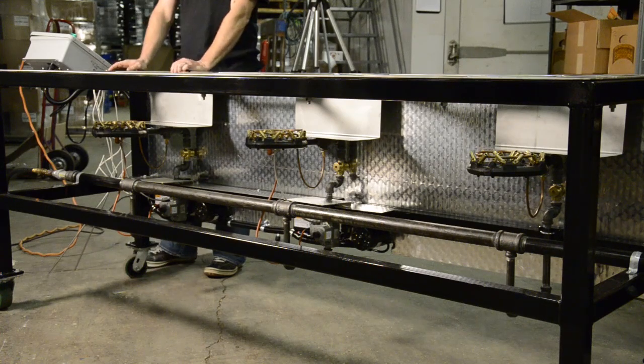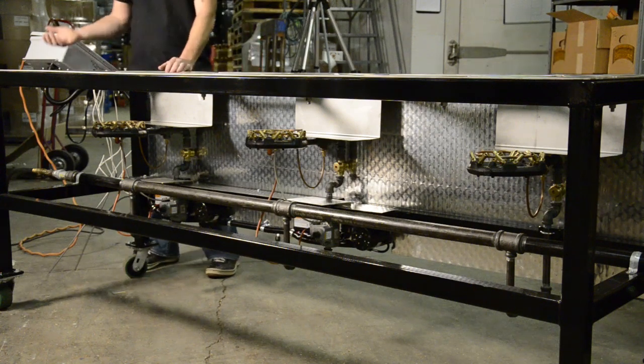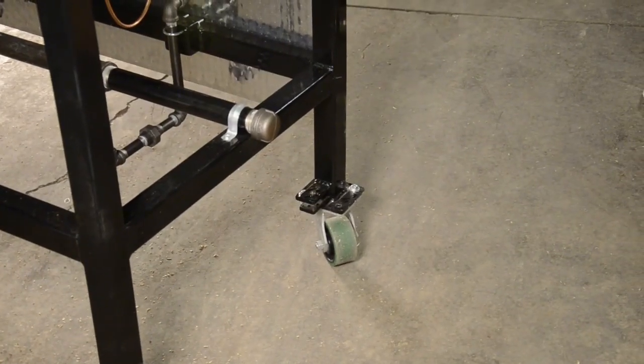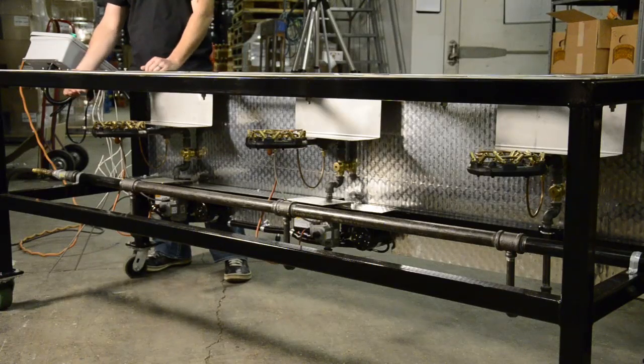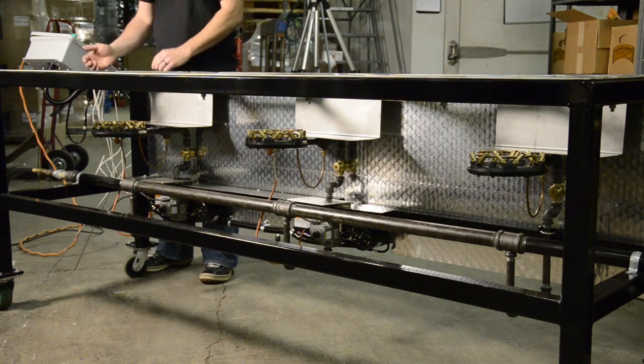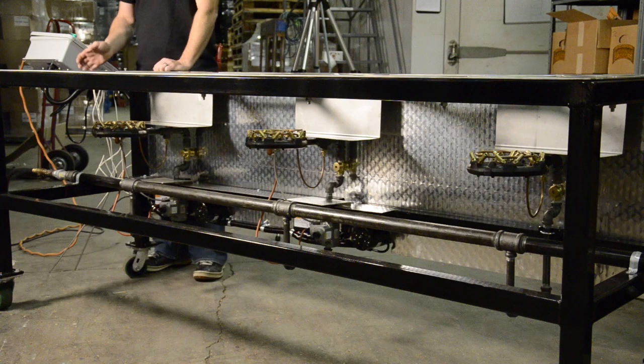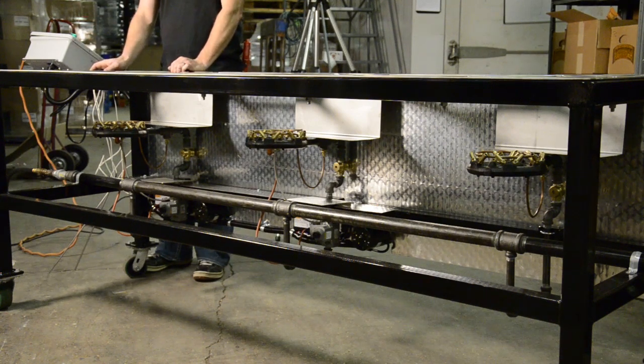Another part of crucial hookup, and to be technical, is your gas supply. The equipment comes with a cap on one end and open fitting on the other to hook a gas valve up and to your building supply. This can be reversed by taking the cap off and flipping it to the other side. It is important that you meet all mechanical codes in your installation, including gas pipe sizing and proper supply pressure. Propane requires a minimum of 10 inches of water column, no more than 13.5. Natural gas, a minimum of 7 inches of water column, no more than 13.5.